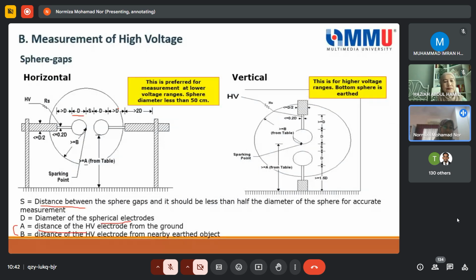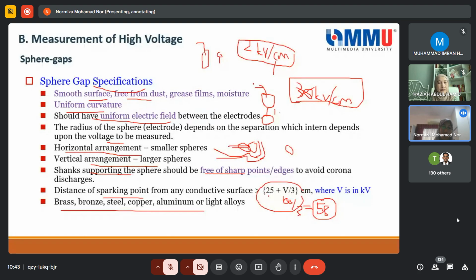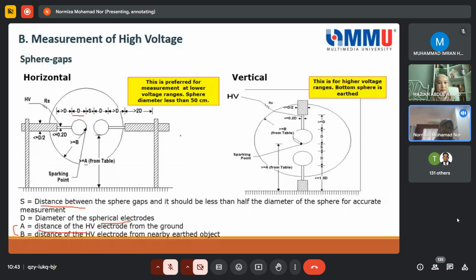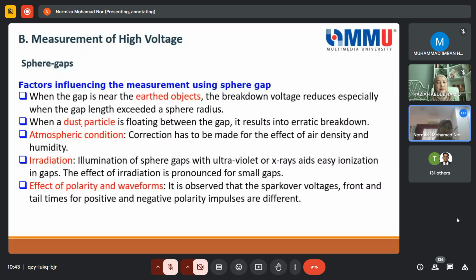In other words, if you refer to this diagram, it is also influenced by this sparking point, the distance from the B. Because you have to fulfill the requirement, which is 25 plus V over 3 as what you've seen before. But if you do not fulfill this, and somebody is standing here, or there's nearby equipment very near that does not fulfill that formula or requirement, then you may see that the voltage here will not be accurate. It will give you the breakdown at lower voltage. So this is a disadvantage, because it's very much influenced by other factors.